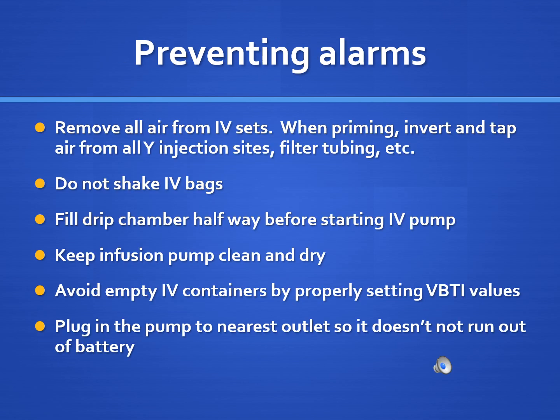So preventing the alarms from sounding is key because it's going to avoid interruptions for you as a nurse and for the patient. So you'll always want to be sure that the tubing is primed properly, ensure there's no air in the tubing. You always want to make sure the IV bag is not really cold or really hot. Never shake the IV bag. If it's a mixed bag, just invert it gently to mix it.